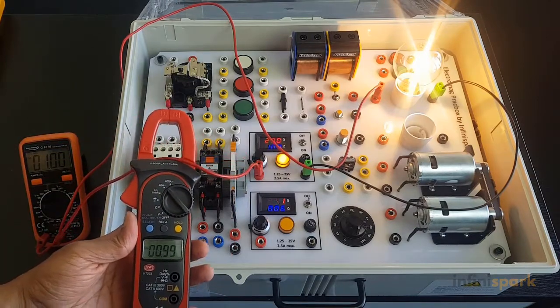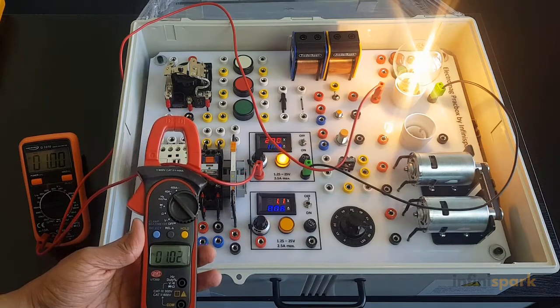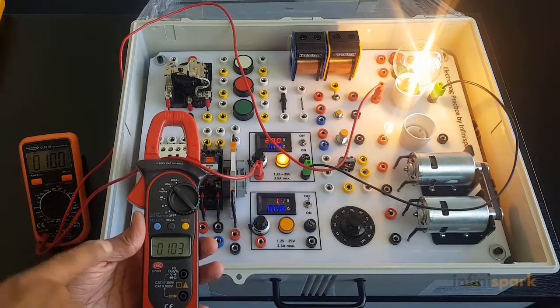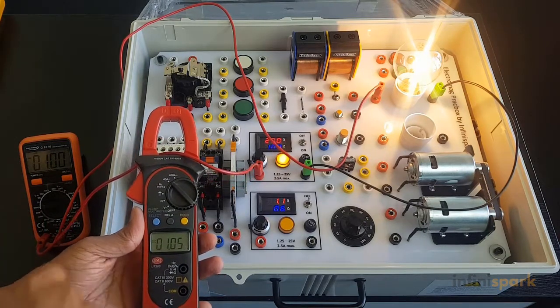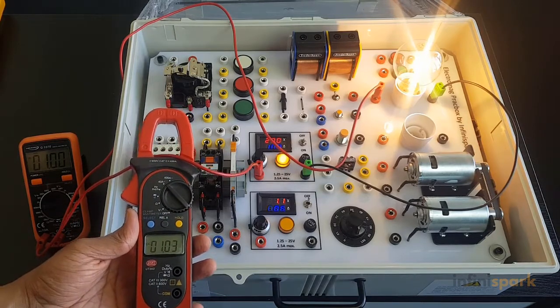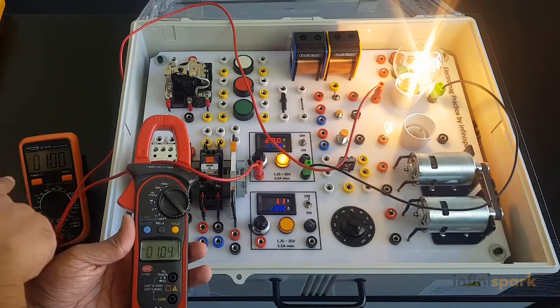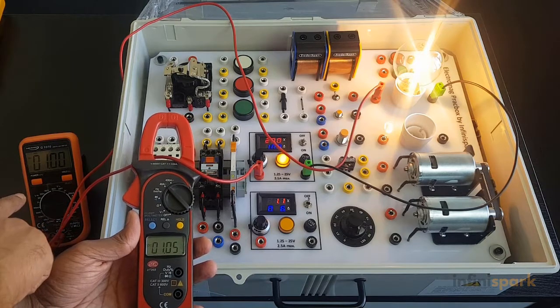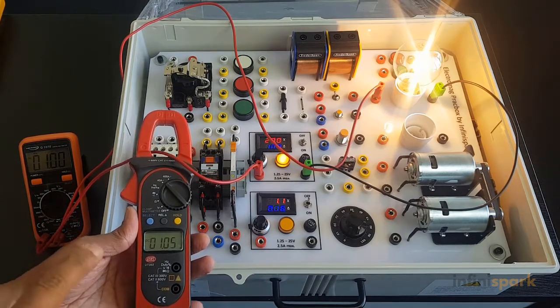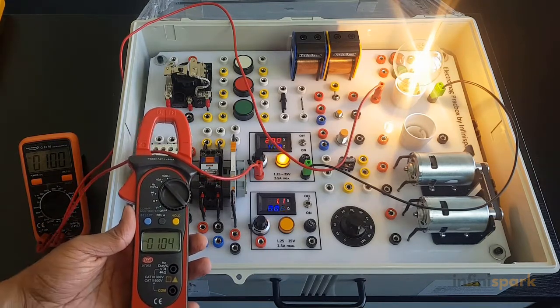Then I'll be able to measure the current that is going through that circuit. So you can see how we've got 1 amp there and about 1.05, so there is a little bit of error there. You can see how for an inline ammeter, I had to disconnect the circuit and force it through the meter. For clamp-on ammeter, all I needed was the wire.